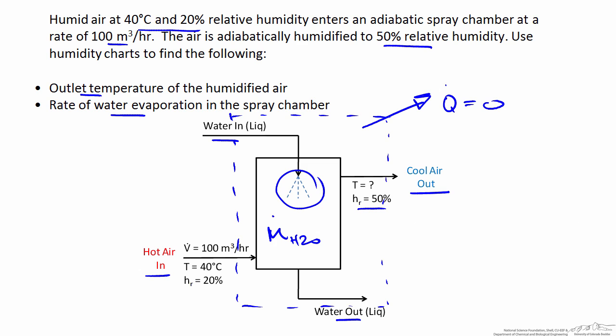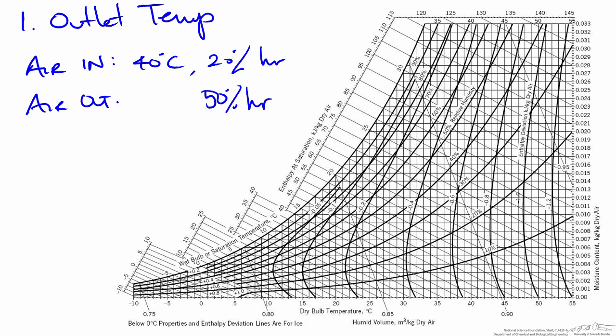So to find the outlet temperature of the humidified air, we'll go to the humidity charts to see how this process works. I've shown a reprint of the humidity charts in SI units. We know the air going into the spray chamber is 40 degrees, and that can be found on the x-axis where the dry bulb temperature is shown. So this is the temperature that would normally measure with a thermometer, and we're at 40 degrees going into the chamber. We also know the relative humidity is 20 percent, which is along this curve. So the air entering the spray chamber is represented by the intersection of these two points at approximately right here.